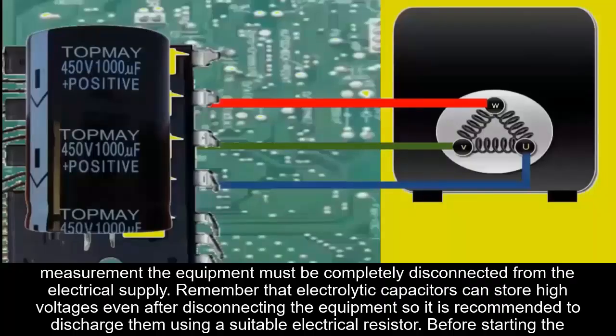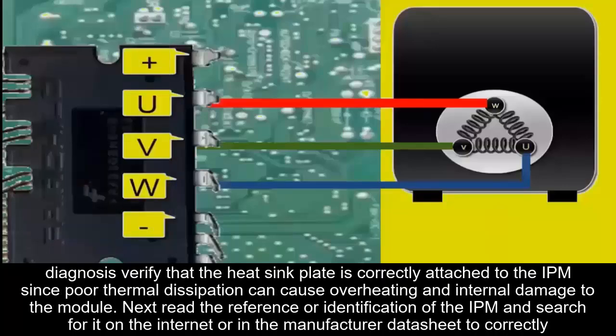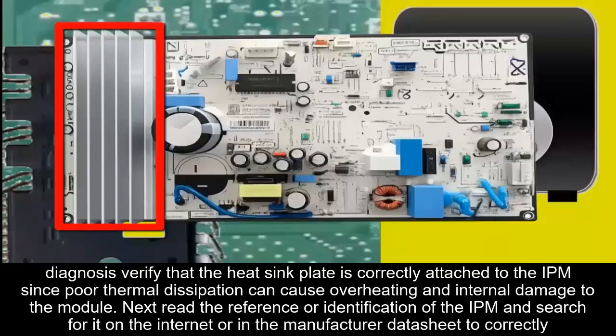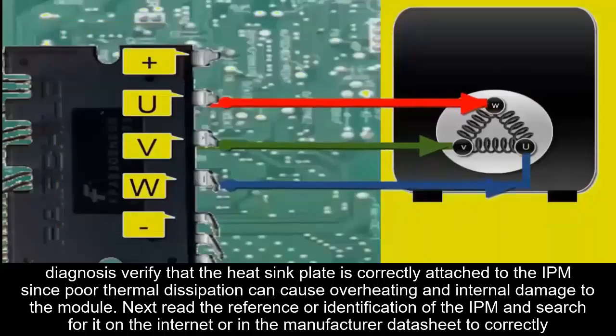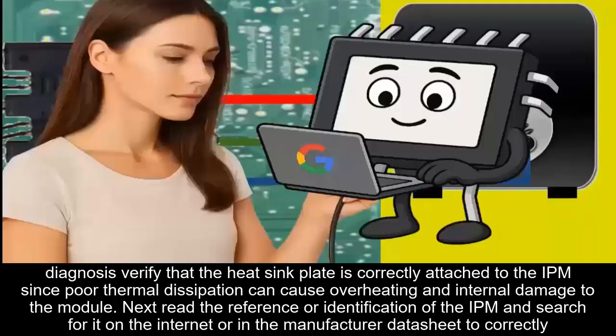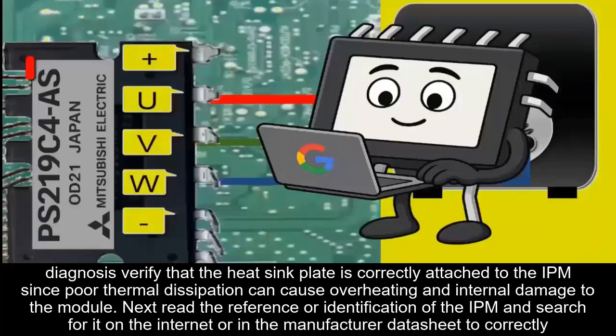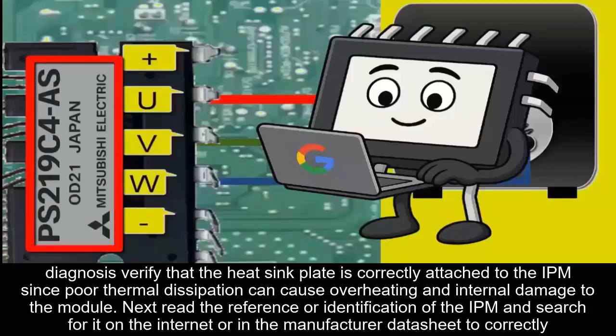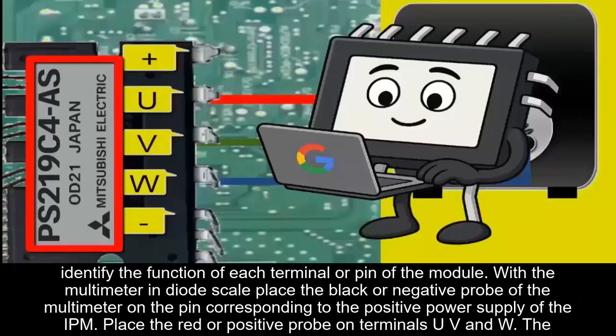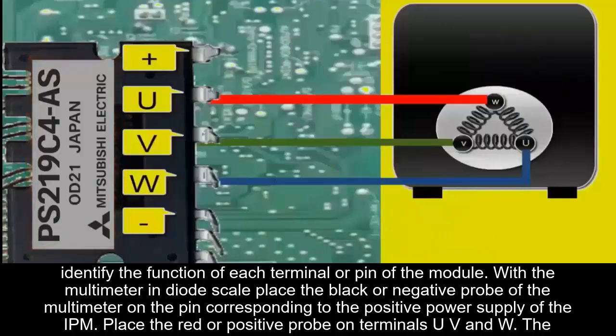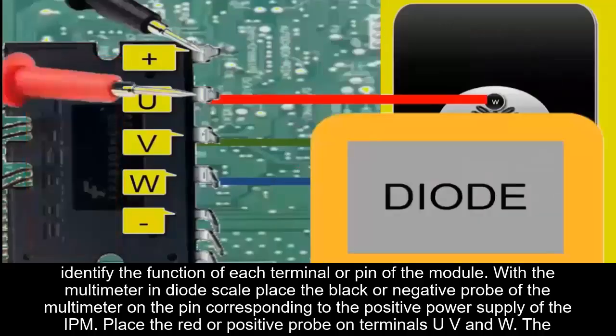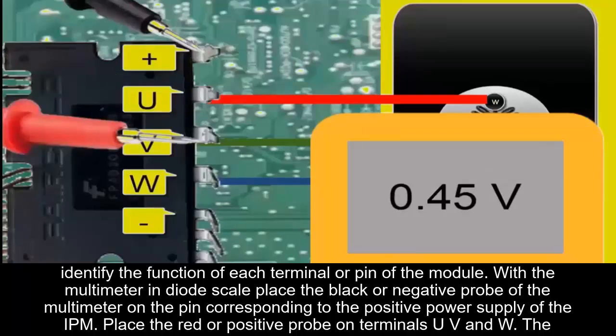Before starting the diagnosis, verify that the heatsink plate is correctly attached to the IPM, since poor thermal dissipation can cause overheating and internal damage to the module. Next, read the reference or identification of the IPM and search for it on the Internet or in the manufacturer's datasheet to correctly identify the function of each terminal or pin of the module. With the multimeter in diode scale, place the black or negative probe of the multimeter on the pin corresponding to the positive power supply of the IPM.